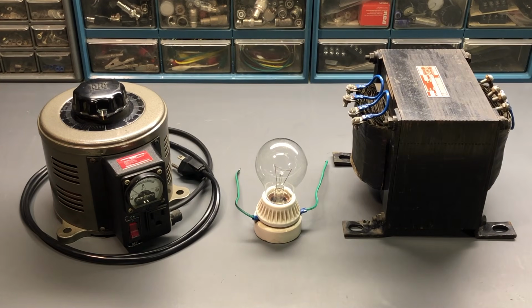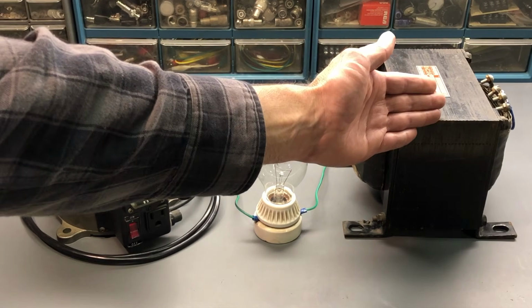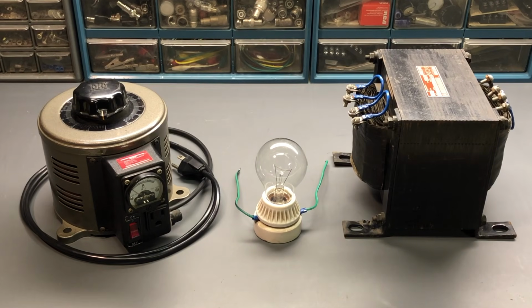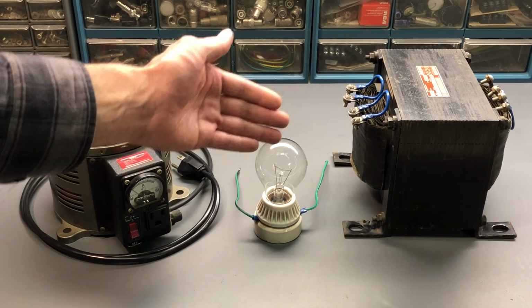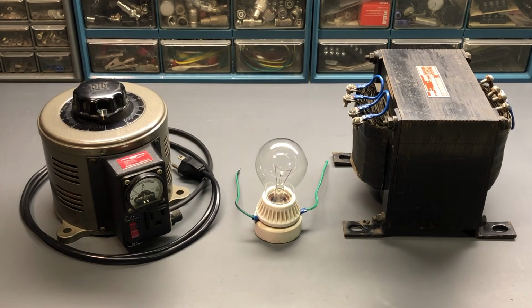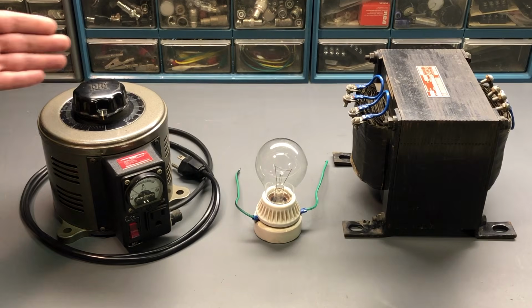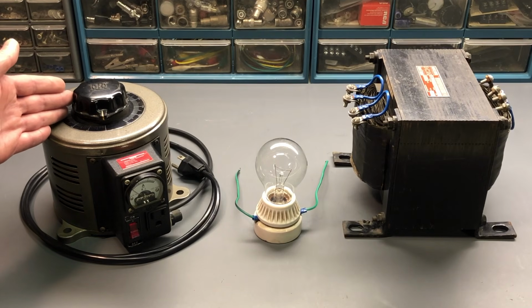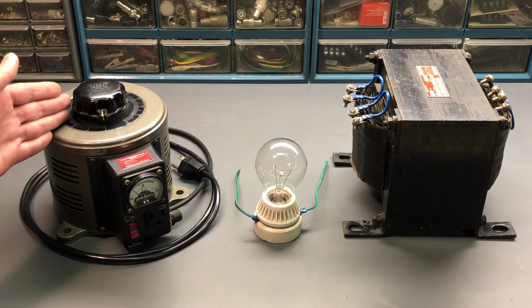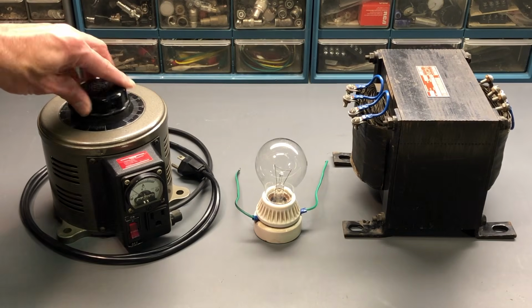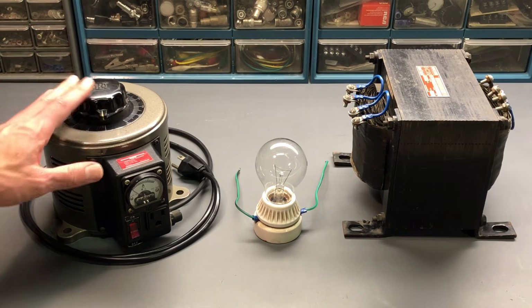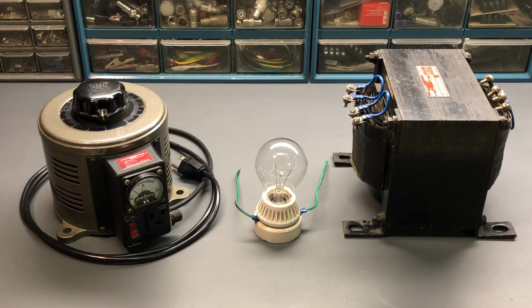Here we are looking at the three main components of an isolated dim bulb tester. On the right-hand side we have the isolation transformer, which provides electrical isolation on the AC line. In the middle is the incandescent bulb, which offers the current limiting. And on the left-hand side we have the Variac, which is a type of autotransformer, and that allows us to vary the AC voltage going to the device that we're powering.